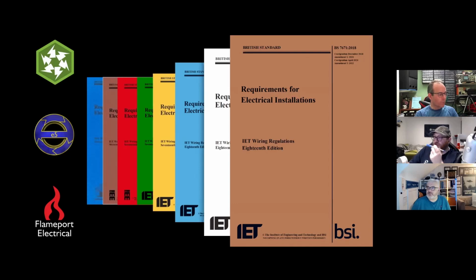So I mean, could you just do testing maybe to kind of determine? Yeah, you can, just to see if it's extraneous. But bearing in mind that if it's going to the boiler and the boiler's connected to the installation through the mains lead, you're going to have to disconnect that first, because obviously it's still connected. So yeah, can be a bit of a bother. Ideally, you want the situation where it's a plastic oil tank and then it doesn't apply because the ends aren't attached to anything conductive.